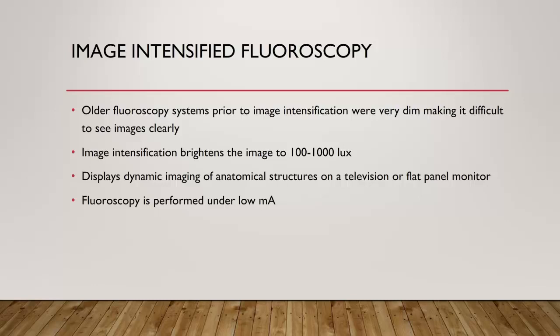The image intensifier is as the name implies. It will intensify the image and in this case increase the brightness many times over. It is like walking into a room that is completely dark. It takes a few minutes for your eyes to adjust so that you can see. This is what occurred with radiologists prior to image intensification.